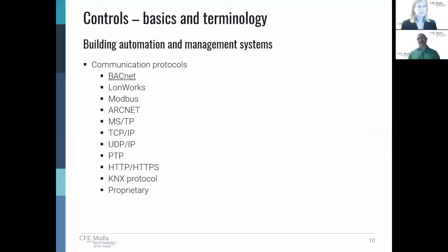And Modbus is a similar version. It can sometimes take the place of BACnet in very small systems. But it's a digital communication protocol where you use a twisted shielded pair, and I can gain a variety of points and access. Electrically, we use Modbus commonly for generators and transfer switches, paralleling gear and the like, where we want to communicate more than just a single point. It can be more cost effective, for example, than running individual wires to get 12 individual points. I can just run a twisted shielded pair and have BACnet or Modbus.